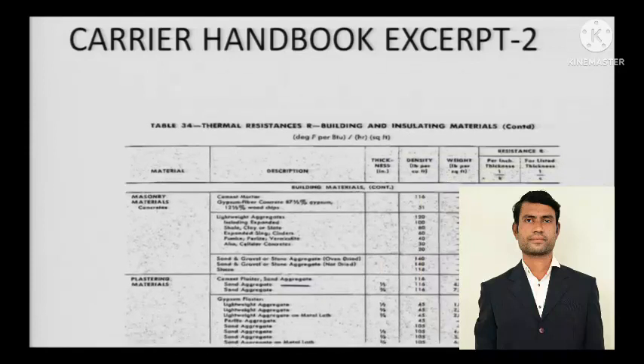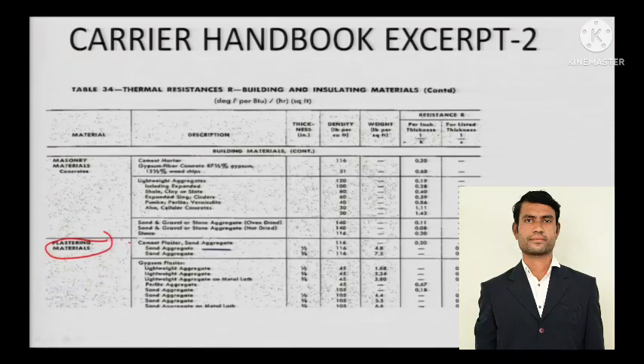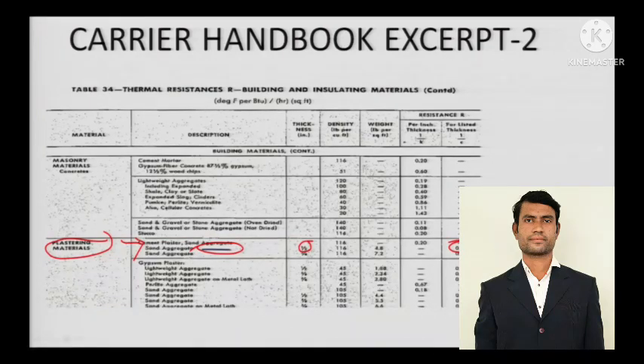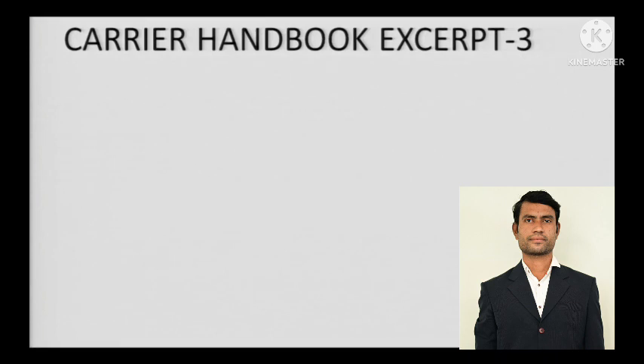This is the second page of the Carrier Handbook — not available in general textbooks. For thermal resistance of plastering materials, we look at cement plaster with sand aggregate. For half an inch of thickness, the resistance is 0.2. If it is 1 inch, multiply by 2, and so on. You multiply continuously by the appropriate factor to get the resistance for whatever plaster thickness is on your wall.